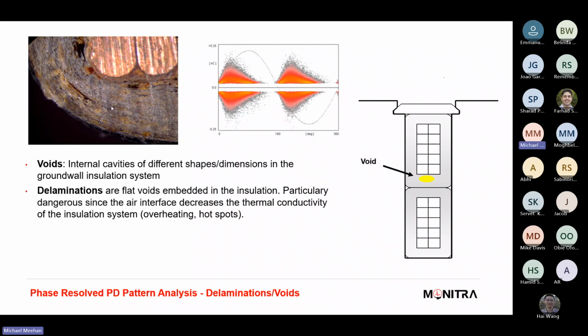So here we've got a picture in the top left where you've got the insulation around the copper of the machine, and there's internal cavities of different shapes and dimensions around the ground wall insulation. So obviously you've got your insulation between your conductor and your frame or your ground wall, and these voids, even though they don't maybe look like too much of an issue, they will charge, they'll conduct, and over time you will get tracking, you will get a breakdown between the conductor and the ground wall, and that's when you do get the problems of a flashover, and potentially if it's a significant flashover, a potential rewind, or more, depending on the motor type. It could be a brand new motor based on the cost of repair.